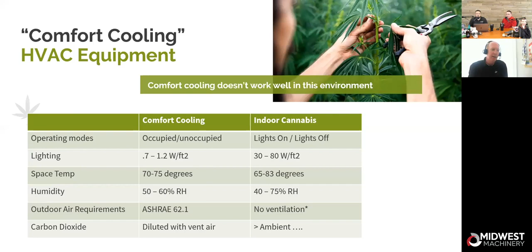Again, if you did have ventilation, how does that impact CO2? One of the things that we've talked about with CO2, we're doing CO2 injection into the cannabis rooms because people have figured out that CO2 absorption, when it's at 1,200 to 1,500 parts per million, you get better plant growth. You get quicker plant growth. Normally occurring CO2 is about 400 parts per million. So if you bring in a lot of ventilation air, you're going to go through a lot more CO2 trying to maintain a higher CO2 level. So certainly that's a big difference from the comfort cooling side of the equation. There are some significant differences there, and as we get into it, you'll see more about it.